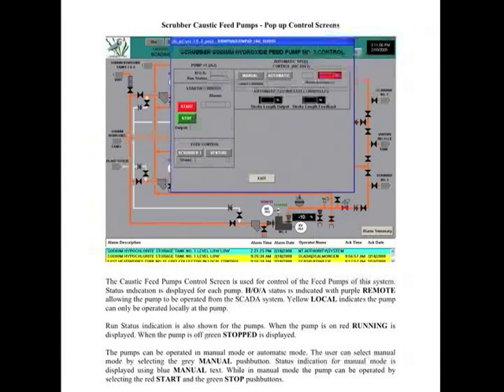In the case of pump 2, and in the case of pump 3, you're going to have the choice of pumping to scrubber 3 or the Venturi. When it says Venturi, it basically means recycle tank. Now, currently on the recycle tank, you have 2 modes of control. You have the ability to run it off of pH control from your pH probes over there in your recycle tank.